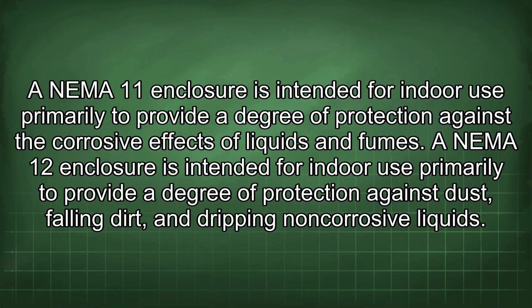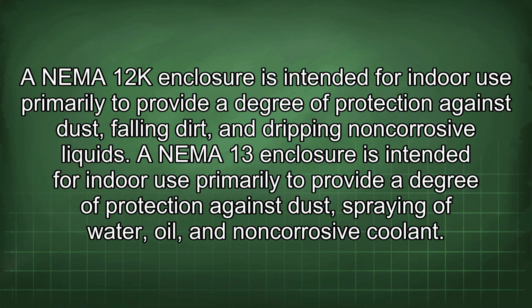A NEMA 11 enclosure is intended for indoor use primarily to provide a degree of protection against the corrosive effects of liquids and fumes. A NEMA 12 enclosure is intended for indoor use primarily to provide a degree of protection against dust, falling dirt, and dripping non-corrosive liquids. A NEMA 12K enclosure is intended for indoor use primarily to provide a degree of protection against dust, falling dirt, and dripping non-corrosive liquids. A NEMA 13 enclosure is intended for indoor use primarily to provide a degree of protection against dust, spraying of water, oil, and non-corrosive coolant.